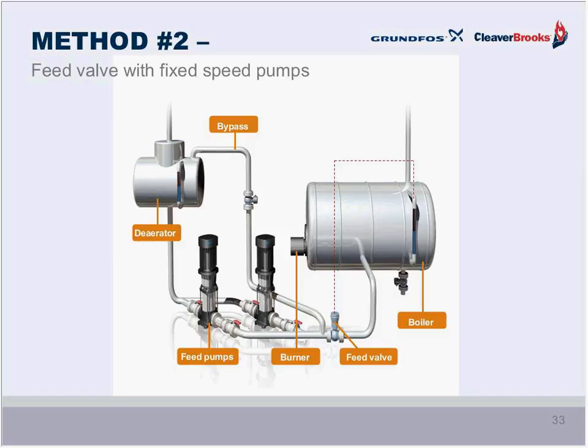But this method requires that instead of having intermittent duty pumps, they have to be continuous operation. So we have a bypass line that goes back to the deaerator tank. You can see that going from the discharge header. It could be a vented feed tank in addition to a deaerator, by the way. It could be either or. So there's a bypass line.